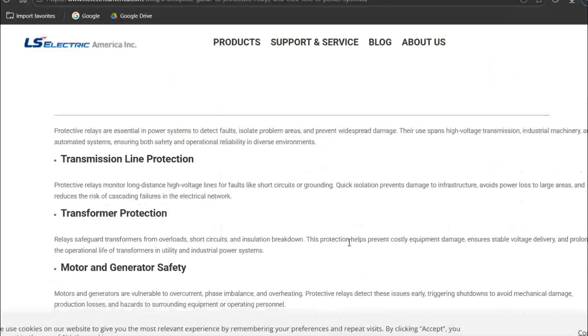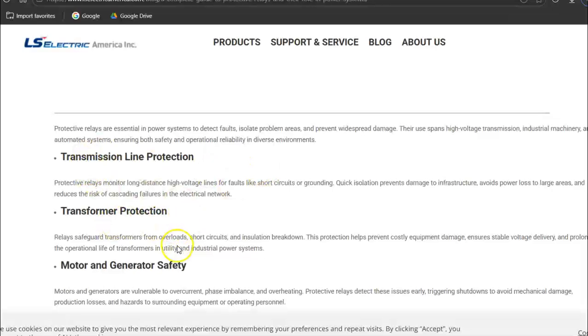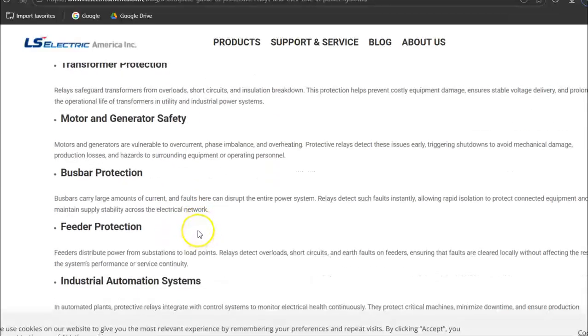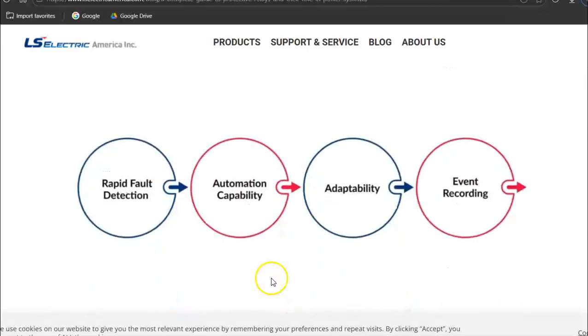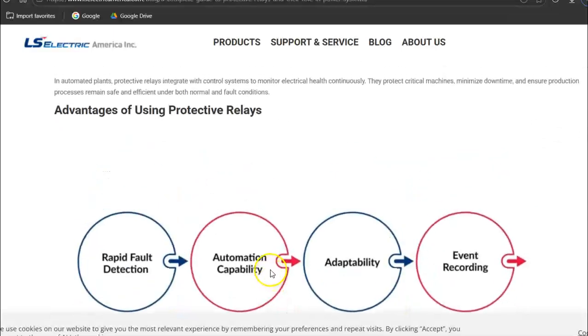So what are these used for? Just about everything. Transmission protection lines, transformer protection, motor generator safety, bus bars, feeders, industrial automation systems. And the advantage of some of these newer ones, and you're going to get a whole course on these in protection and control, is the intelligence. You program everything. They have all their inputs, they have all their outputs. As I say, it's very much similar to a specialized PLC.